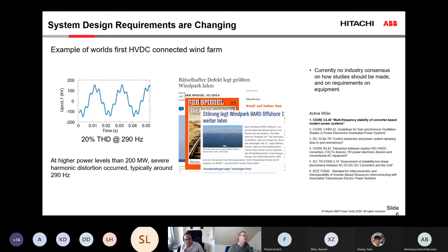And it resulted in very long outages. We at ABB, which was what the company was called at the time, dimensioned those filters for 5% harmonic distortion, believing we would have a safety factor over 2. But when they were exposed to 20% THD, the filters were damaged and caused long outages to the station. And at that time, there was not really a good understanding of the types of problems we are talking about today. It's now a very, very important academic and industry problem. You can see here a list of active working groups looking into controller interactions and these things.